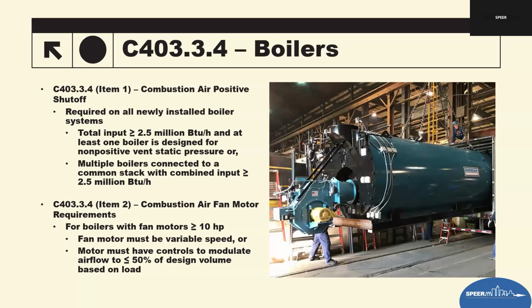And then item number 2, we have fan controls, anything greater than 10 horsepower. For boilers with combustion air fan motors 10 horsepower or greater, the code now requires them to be either a variable speed fan motor, or controls that can modulate air down to 50% of design flow based on boiler load. So this is about matching combustion air volume to actual fire rate. Older boilers often run full airflow regardless of the firing level, which wastes a ton of thermal energy as well. These new controls now ensure the system modulates and operates more efficiently.